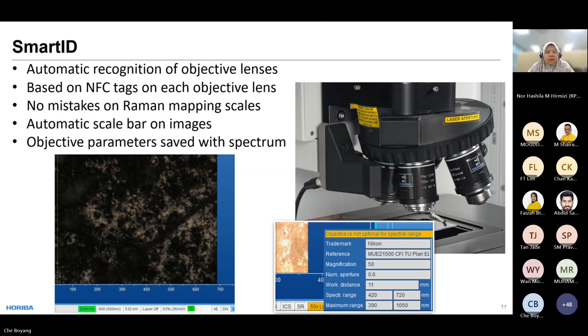With the Raman microscope, we can also extend the capability to do mapping, or what we call a Raman image. To do that, we have to include a motorized stage. A motorized stage means you can move your stage in both X and Y automatically. With the motorized stage, we are able to map a sample, which means instead of just measuring one single point, we are able to scan an area. Within this area, we scan point by point with the moving stage, so at each point you can have one spectrum.